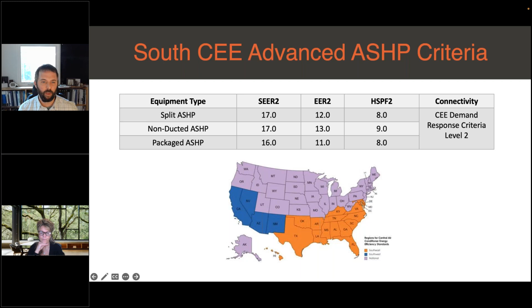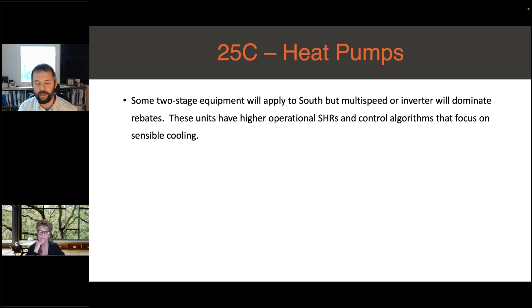So what does all that criteria mean for 25C? It basically means the CEE requirements are going to drive us to multi-speed and inverter equipment. Typically this equipment has higher operational SEERs, and the control algorithms are really slanted at meeting that test requirement and getting the high SEER, high EER2. Some manufacturers are better than others, in my experience, with their algorithms to help control latent removal. But if your set point and your measurements are entirely based on temperature, it more than likely is not going to do a great job controlling humidity.